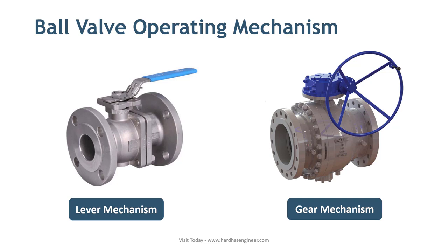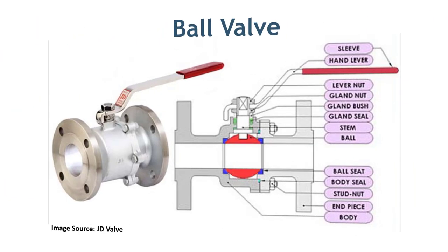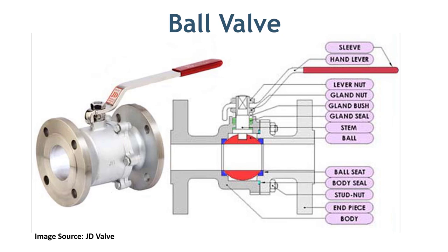The ball valve is like a plug valve in operation. Small size ball valves can be operated by lever. However, for large size valves, you may need a gear mechanism to operate the valve easily. Some degree of throttling is possible with a ball valve, but it is not recommended as it may damage the seat and ball. When fully open, the pressure drop across the valve is negligible.